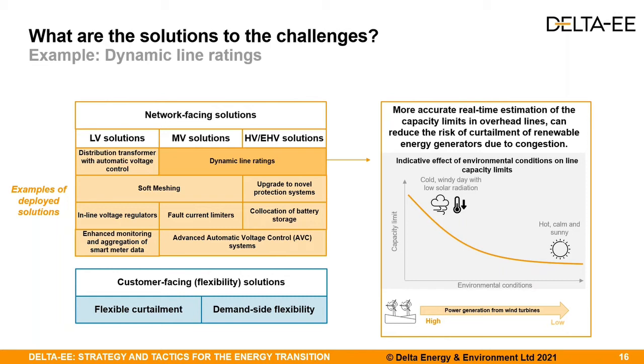So, dynamic line ratings - the whole concept is based on the fact that traditionally, the maximum amount of current that can flow through a conductor line was calculated statically. You would assume extreme static values for variables like wire tension, wind speed, or temperature, to minimize the possibility of overheating the cables.